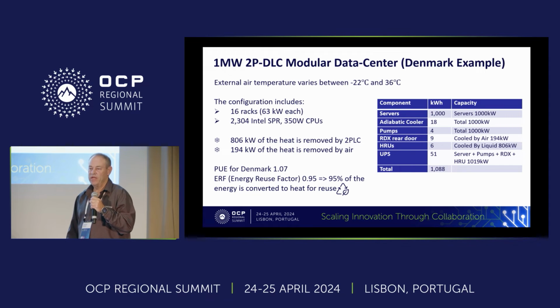When we have evaluated this solution in a location like Denmark, because of the weather, we see that we can get to a PUE of 1.07 in this 1 megawatt data center. And if we're evaluating the heat reuse, we see that we can reuse 95% of the heat at 70-degree water. This is a very efficient way of reusing the heat, because you already have 70 degrees, you do not need to reheat it or anything else. You can provide it directly to building heating. So think of a 1 megawatt data center in every neighborhood for heating up the buildings.